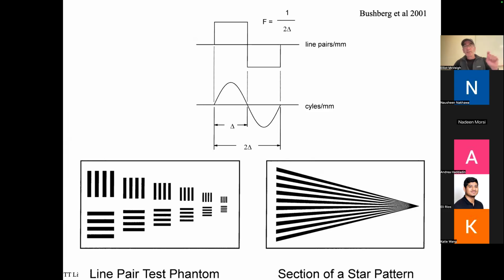And then you have to go in and measure and really establish what is the highest spatial frequency we could measure with that reconstruction or that kernel. That is the signal that changes as a function of space. What's the shortest wavelength that we could actually measure, right? And you can do that with phantoms.